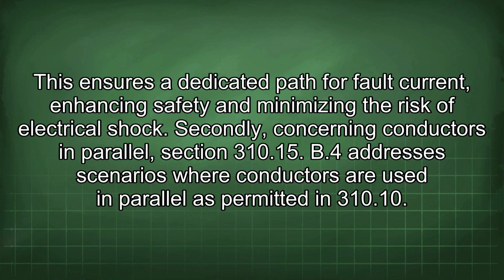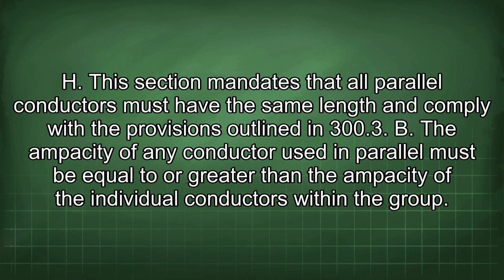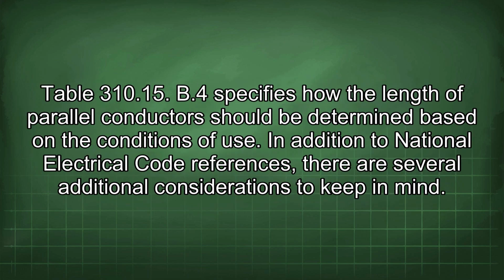Secondly, concerning conductors in parallel, Section 310.15.B4 addresses scenarios where conductors are used in parallel as permitted in 310.10.H. This section mandates that all parallel conductors must have the same length and comply with the provisions outlined in 300.3.B. The ampacity of any conductor used in parallel must be equal to or greater than the ampacity of the individual conductors within the group. Table 310.15.B4 specifies how the length of parallel conductors should be determined based on the conditions of use.